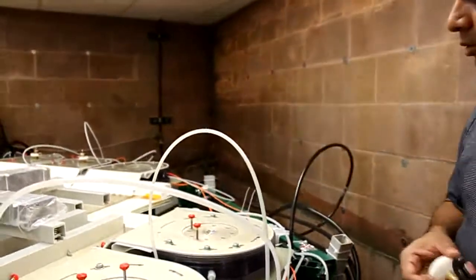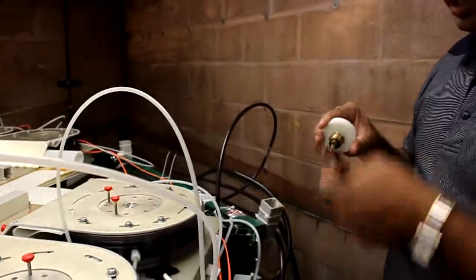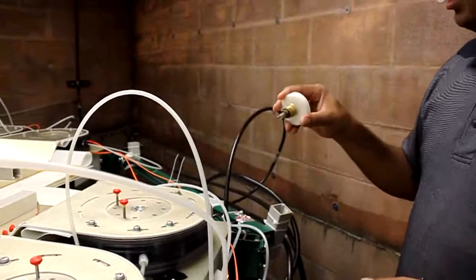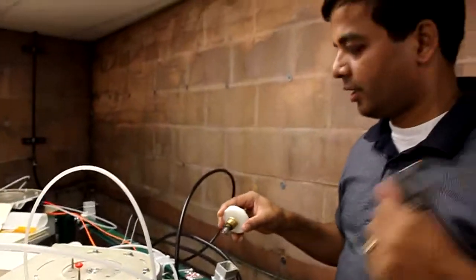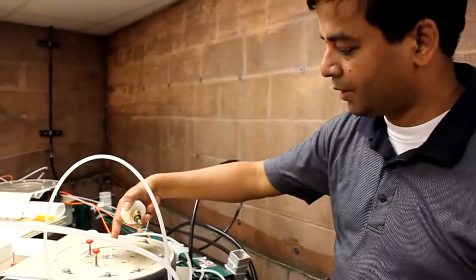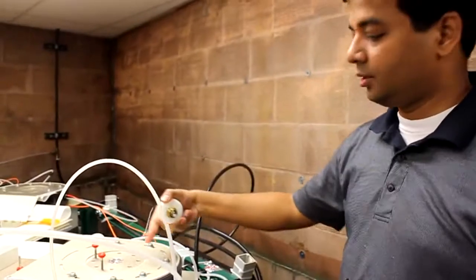The first thing we need to do is measure the spacing and keep the spacing between this step and the bottom electrode constant. So in order to do that, which Eric already did, he measured using the depth gauge the height.